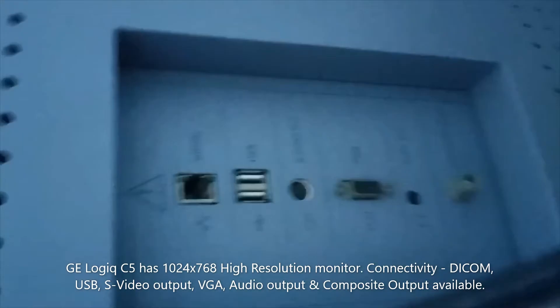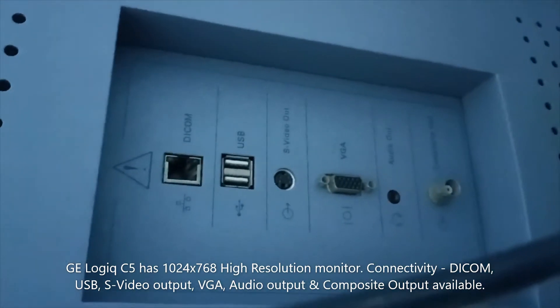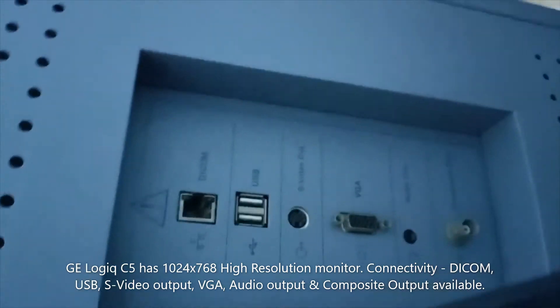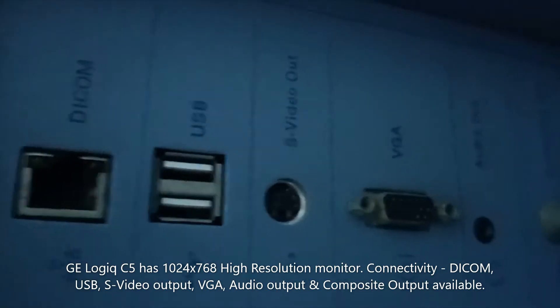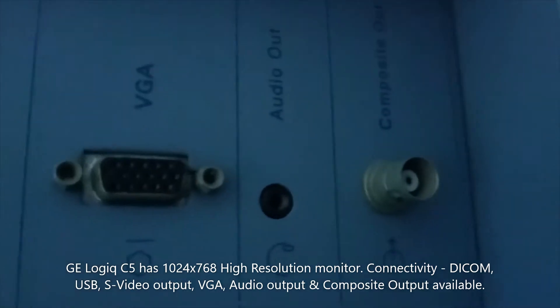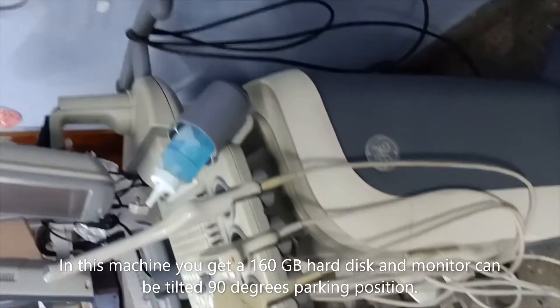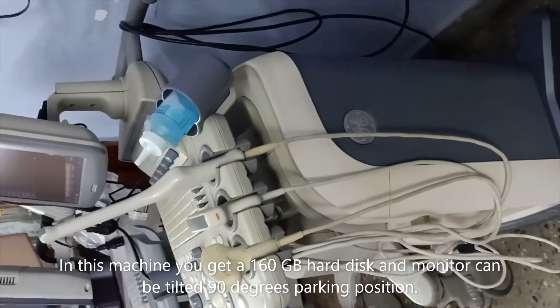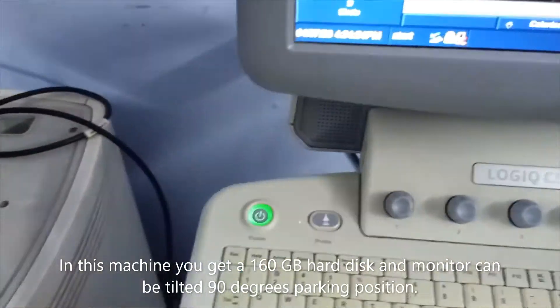This monitor provides a resolution of 1024 x 768 on a high-resolution 15-inch LCD display. For output connectors you get DICOM, USB, S-Video output, VGA output, audio output, and composite output. There is also a VGA-type connector so you can connect another monitor to the machine. This machine has a 160 GB hard disk, and the monitor can tilt to a parking position of up to 90 degrees.